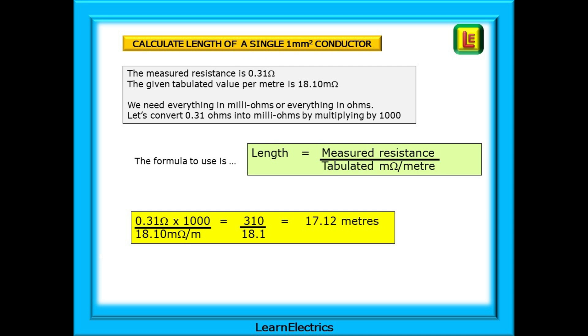The formula to use is the measured resistance divided by the tabulated milli-ohms per meter taken from the table. But we have a problem. The measured resistance is in ohms and not in milli-ohms. The solution? Multiply the measured resistance by 1,000 and convert it to milli-ohms. So our calculation now is 0.31 ohms multiplied by 1,000 and then divide this by 18.10 milli-ohms per meter. And out pops our answer. The length is 17.12 meters long. 17 meters after rounding off.